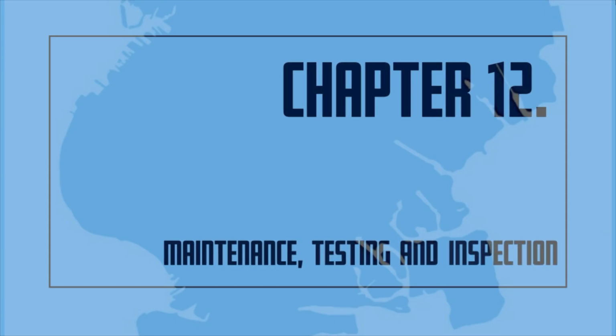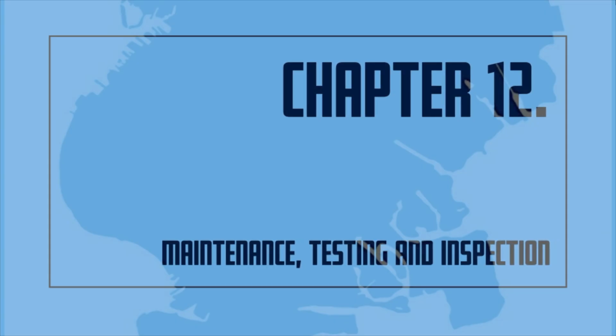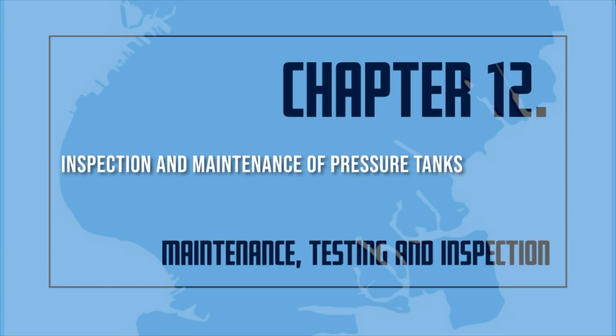Chapter 12. Maintenance, testing and inspection frequencies. Inspection and maintenance of pressure tanks. The water level and air pressure in pressure tanks shall be inspected monthly and maintained in accordance with the National Fire Protection Association, number 25, 2002 edition. The water level and air pressure must provide an adequate water supply to the sprinkler system.